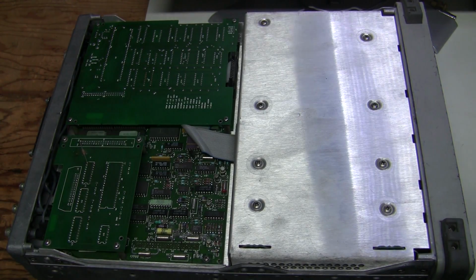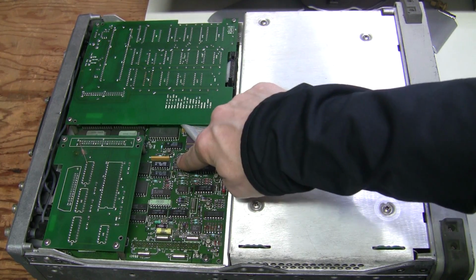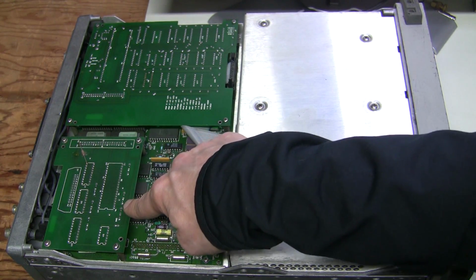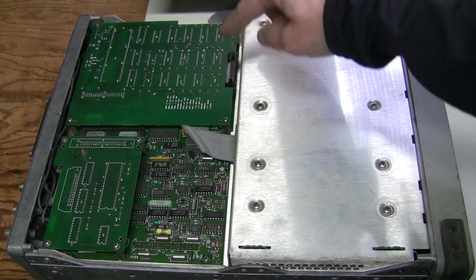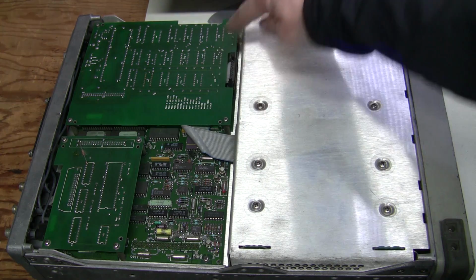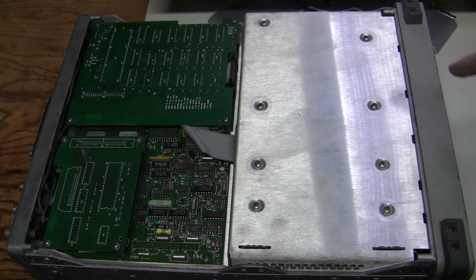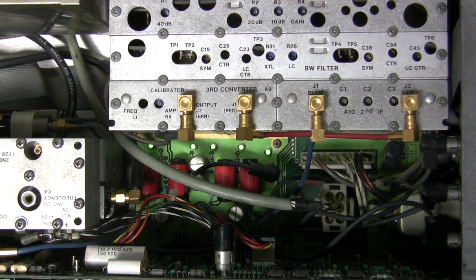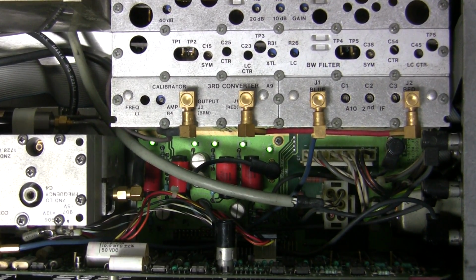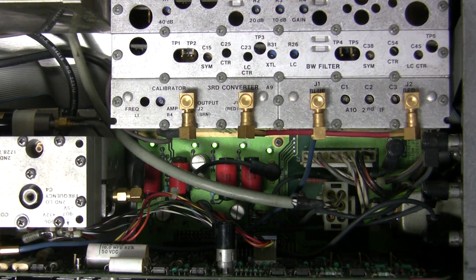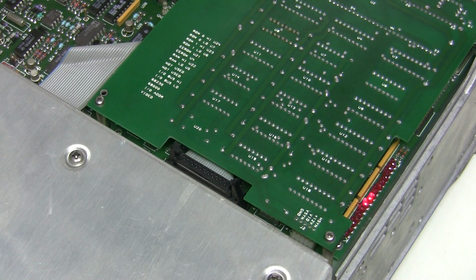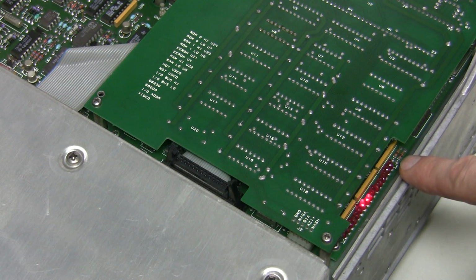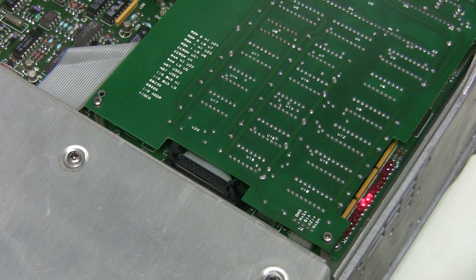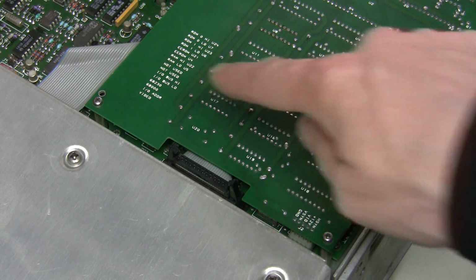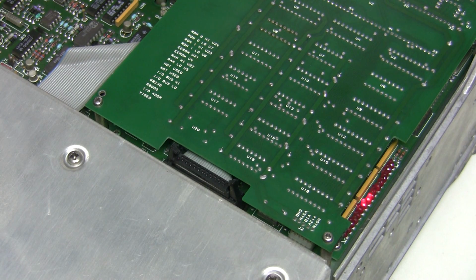And this is the bottom of the unit. Here we have the main processing board. This is optional GPIB board. This is a video board, the output of which goes to the display module. There are power rail LEDs showing that power rails are probably fine, and I measured them. They look fine to me. There are 16 LEDs here on the main board, with explanation over here, and these two, which are on, are not used, and they should be on during normal operation. The rest are off, as they should be, so no problems here.